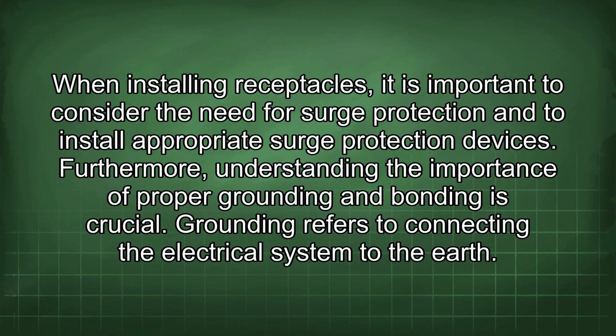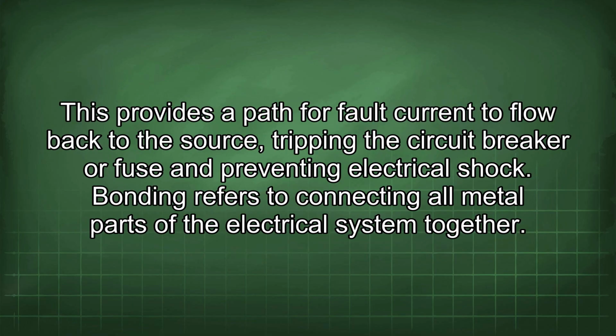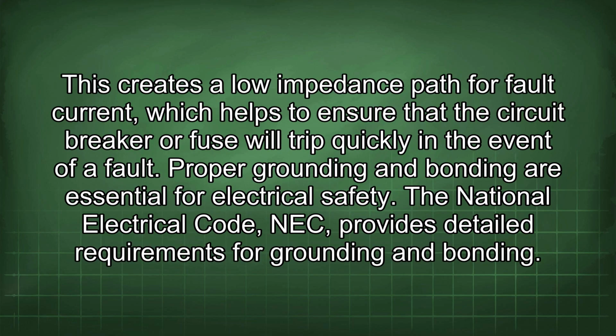Grounding refers to connecting the electrical system to the earth. This provides a path for fault current to flow back to the source, tripping the circuit breaker or fuse and preventing electrical shock. Bonding refers to connecting all metal parts of the electrical system together. This creates a low impedance path for fault current, which helps to ensure that the circuit breaker or fuse will trip quickly in the event of a fault. Proper grounding and bonding are essential for electrical safety.